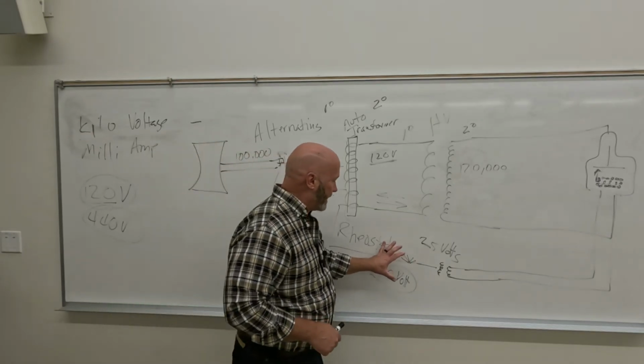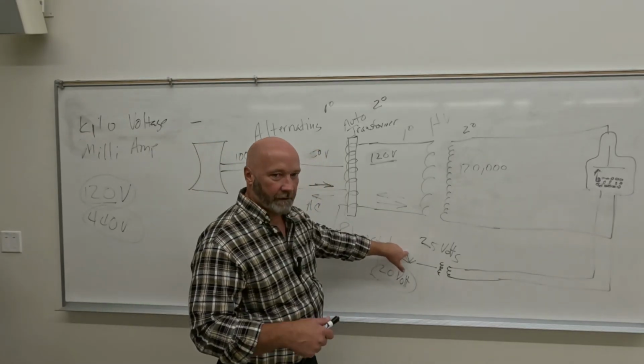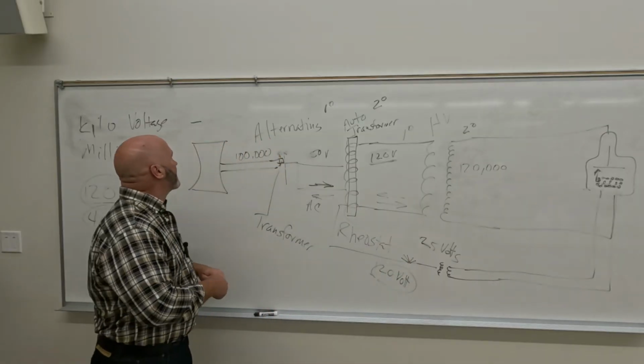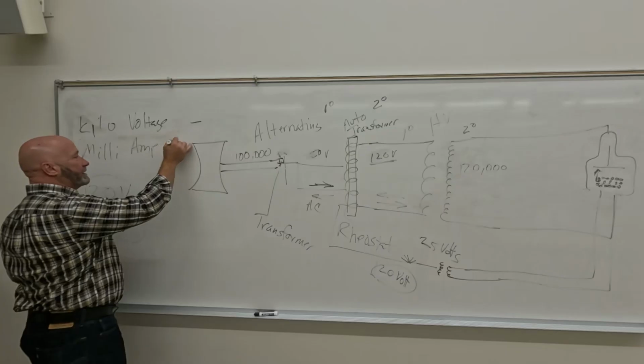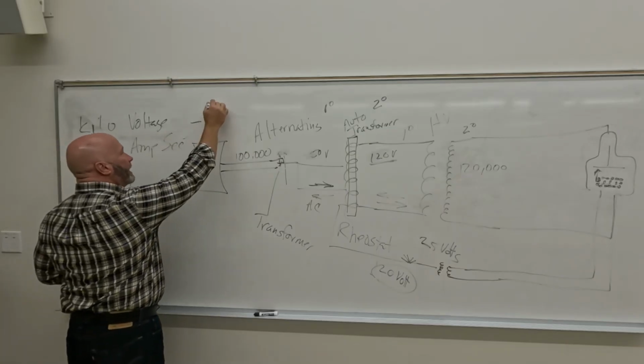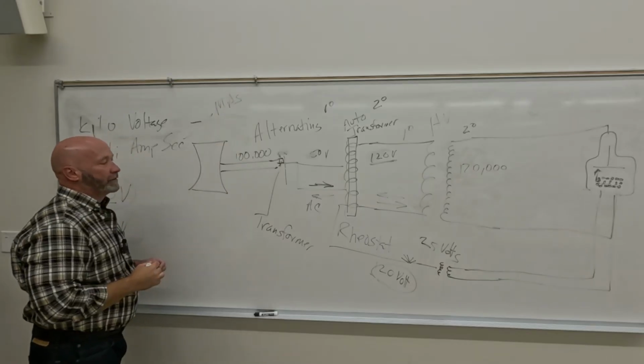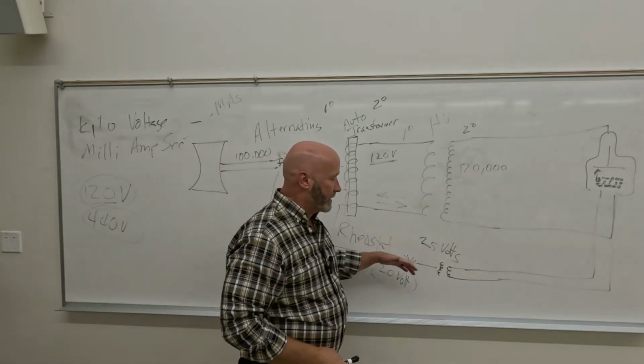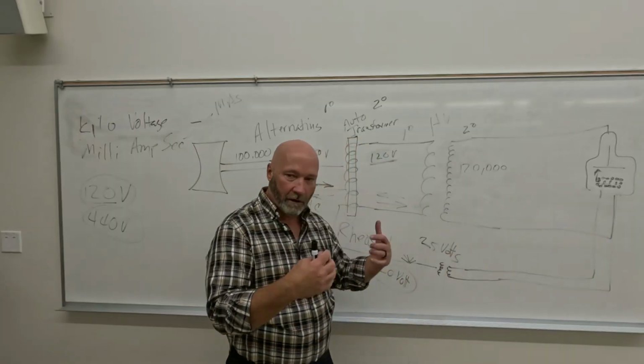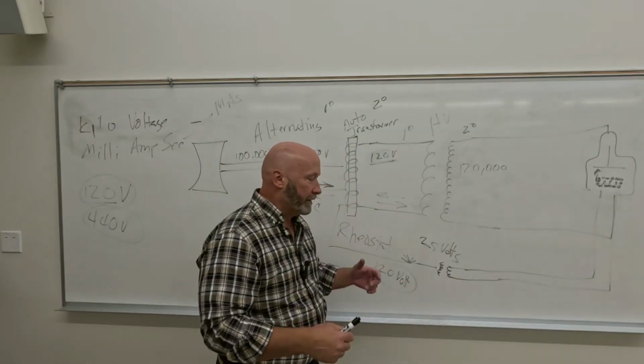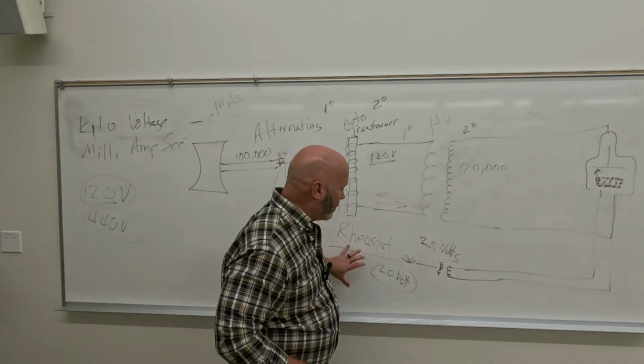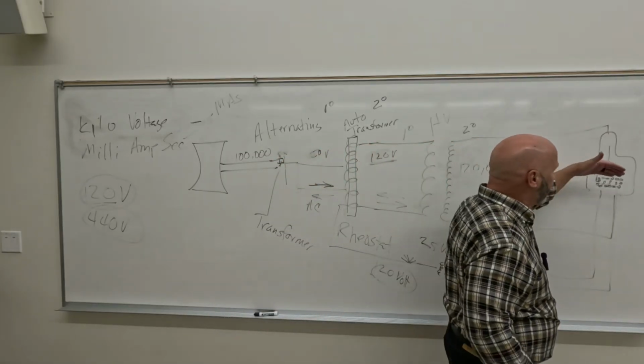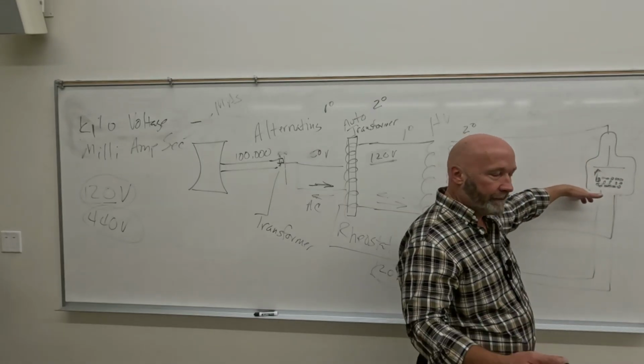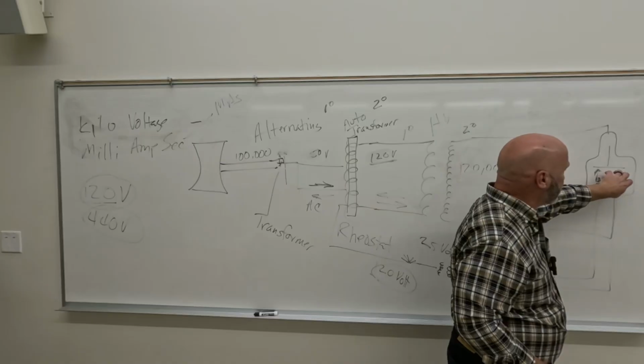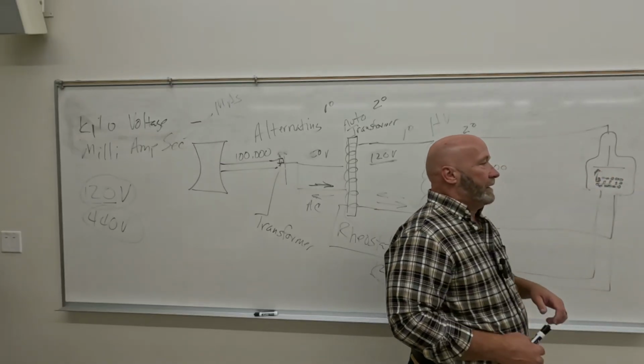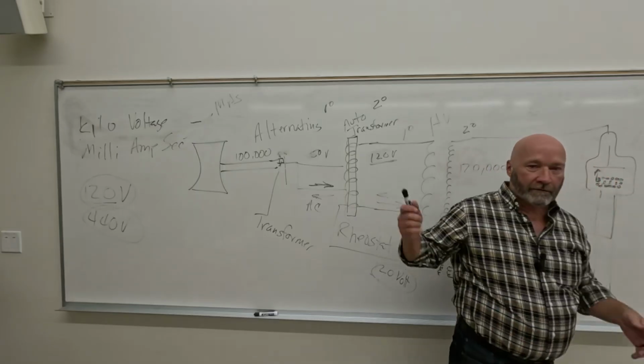All right. Also down here, we've got another rheostat, which is really our mA selector. What you're going to find out is that we have milliamperage seconds, which we're going to refer to as mAs. We have two components to mAs: one is milliamperage, one is the time that you make your exposure. It all goes together to create mAs. More on that later in the semester. But anyway, what this circuit is responsible for is heating the filament to the proper temperature and creating enough electrons on and around the filament to travel across the tube and give us proper mAs.